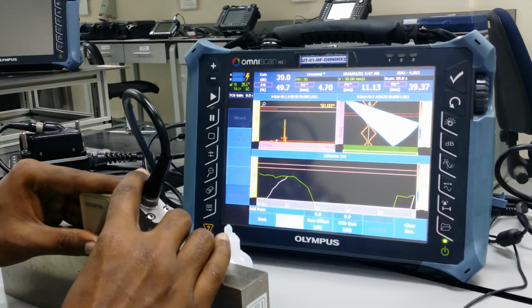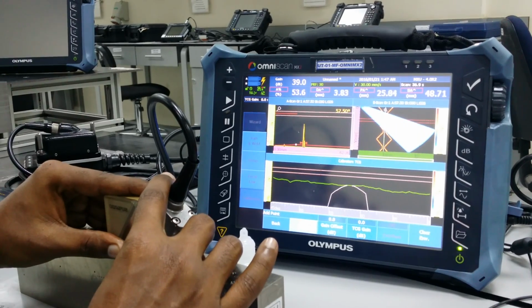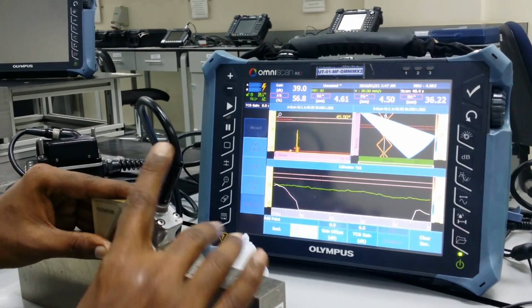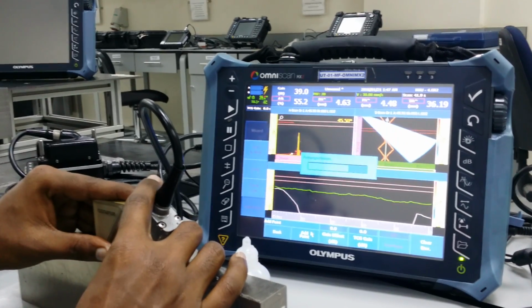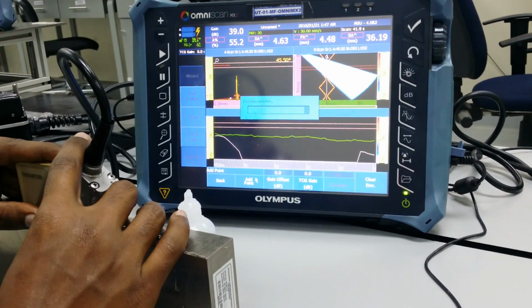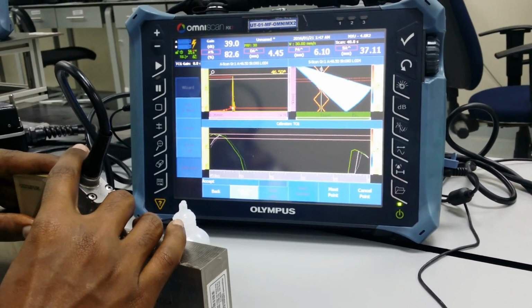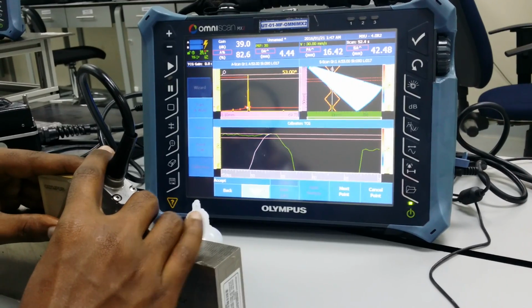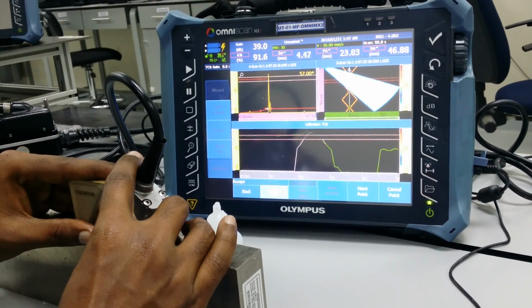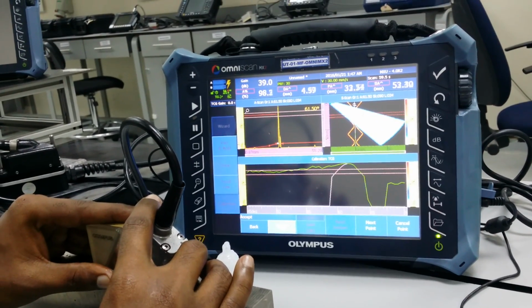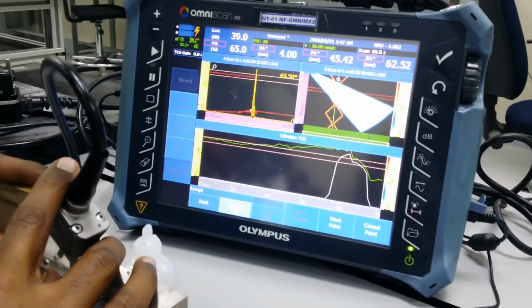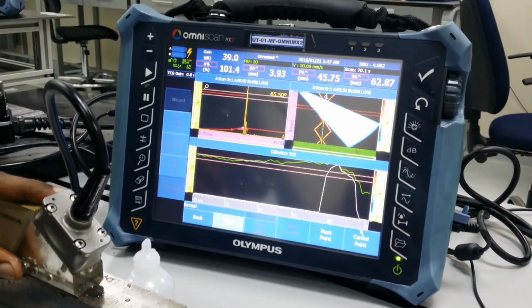Going to the next. Now creating the envelope once again. We'll add the point. So that all the focal laws are getting the same amplitude, 80%, we'll again make the same amplitude point. All the focal laws are getting equal dB. And like we can see, some of our points are not within the appropriate dB. So we'll hit cancel and do this point again.